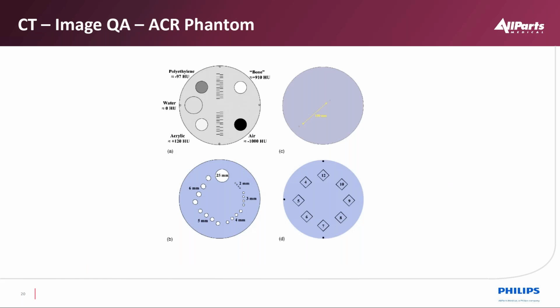Some of the things that we use in the United States is called the ACR phantom. Instead of using distilled deionized water as a source, there's a plastic material that represents what the attenuation coefficient of water would be. So in this phantom, we use it to validate the scanner. This is an OEM independent phantom. It is the American College of Radiology's phantom that we use in the United States.